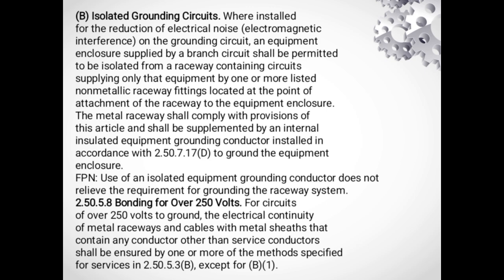2.50.5.8 Bonding for over 250 volts. For circuit of over 250 volts to ground, the electrical continuity of metal raceway and cable with metal sheath that contain any conductor other than service conductor shall be ensured by one or more of the methods specified for services in 2.50.5.3b except for B1.